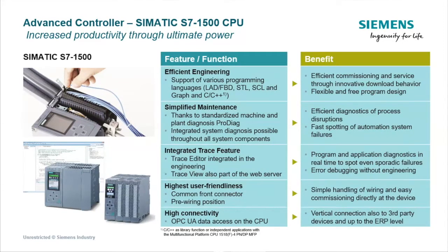We also have an integrated trace feature that is very unique. You don't have to sit on a separate computer connected to the PLC to use the integrated trace. It is all built into the PLC. You set it all up within the PLC, and we're going to show you this in a little bit too. It's actually a common trace editor together with drives, multiple PLCs. It's really nice. It does the advanced mathematics as well, and it gives you the ability to troubleshoot really.